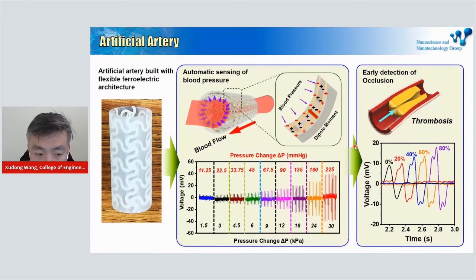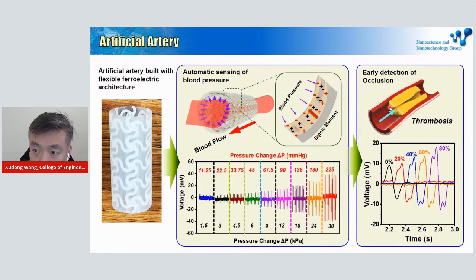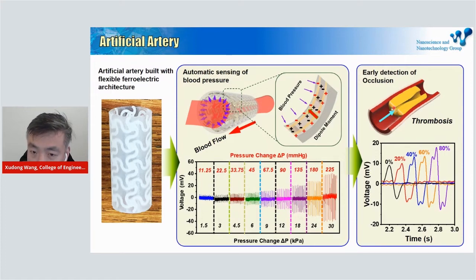More importantly, our three-dimensional structure can very sensitively detect motion changes of the blood vessels. This is very important because it allows us to detect small occlusions or blockages when something builds up inside. As you can see, when there is only 20% blockage in the blood vessel, the output signal starts to drift from a single perfect peak into two peaks, indicating something is happening at a very early stage. This capability will probably save many lives for patients who have had this implantation.